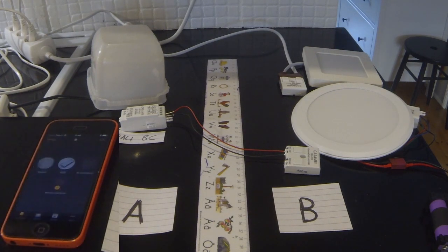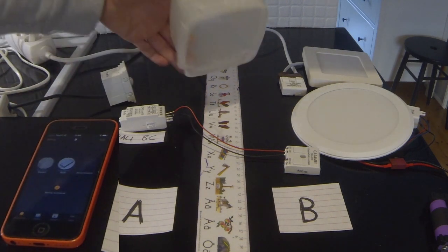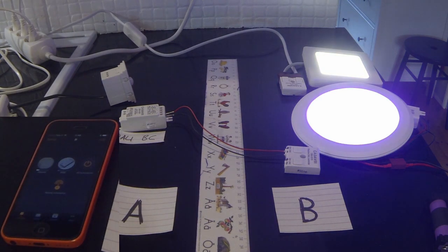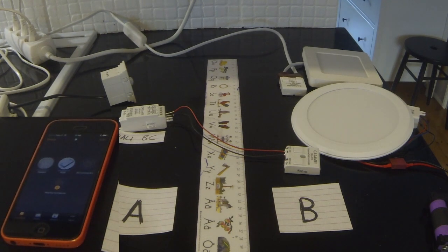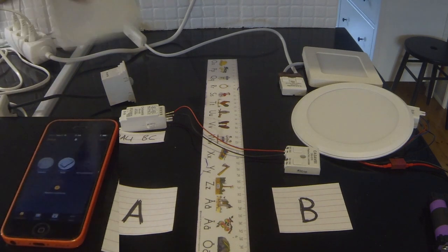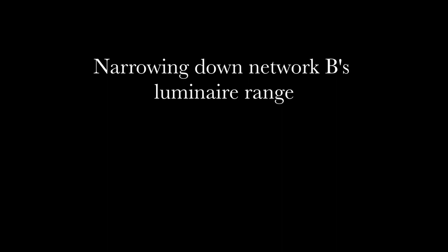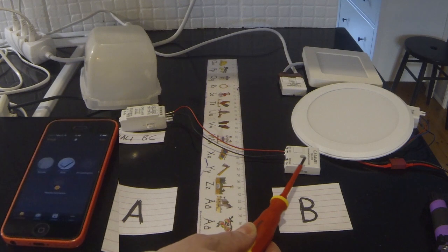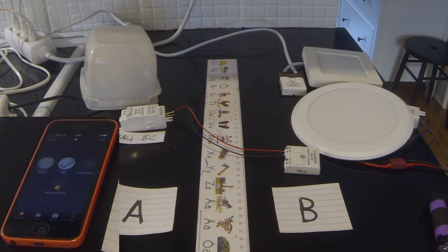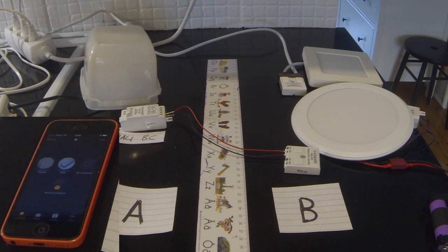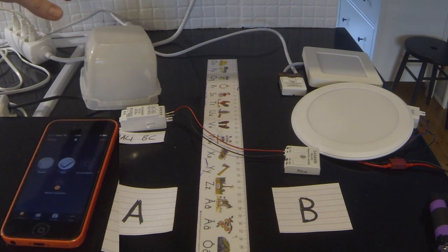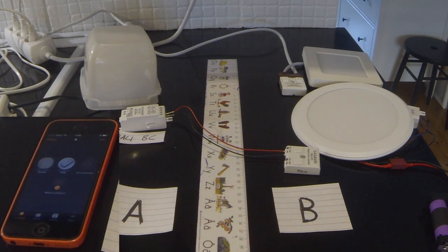I've changed to network B again. So just to show you, this time you should see everything react. I've got the levels very low because the scene that I'm executing actually has the levels of the devices set very low so that the camera doesn't overexpose them. So I'll cover that back over for now. In its default state, this DCS DALI gateway is telling everything. It's forwarding this DALI broadcast message on to absolutely everything in the network. But let's say for instance that we don't want all of the lights to react to this message.